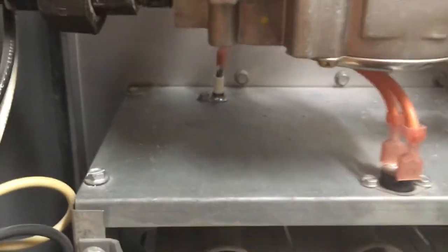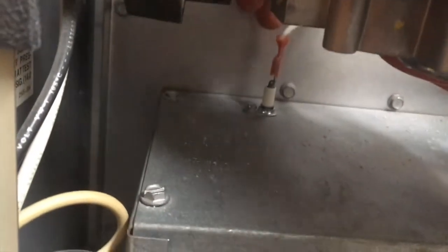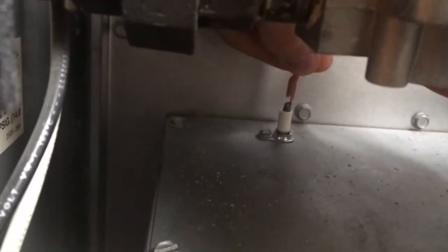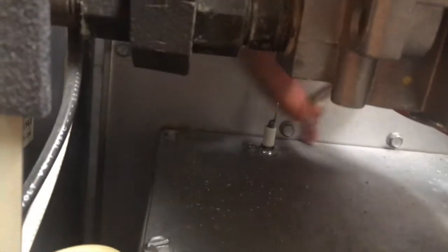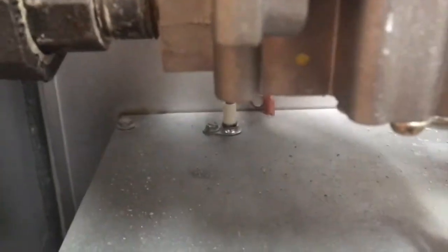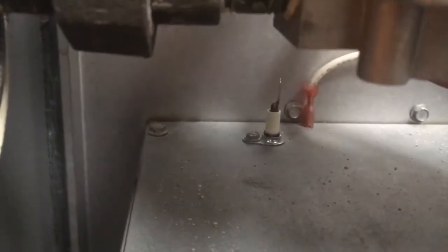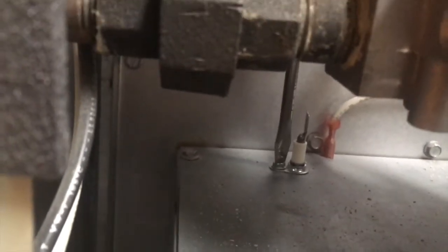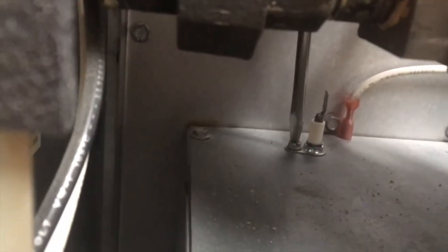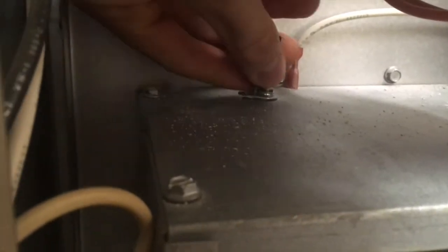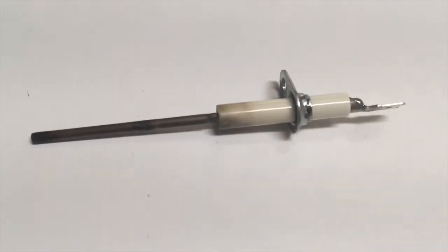So the first thing I'm going to do is pull that wire connector off, disconnect it. Then I'm just going to take a flathead screwdriver and unscrew the screw that holds the flame sensor in. Not much to it, it's just a little probe basically. There's a little residue on the end of it.